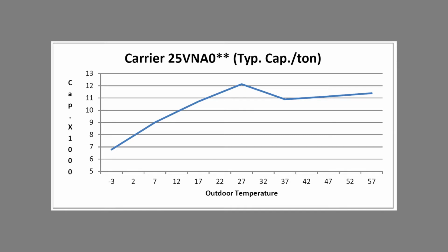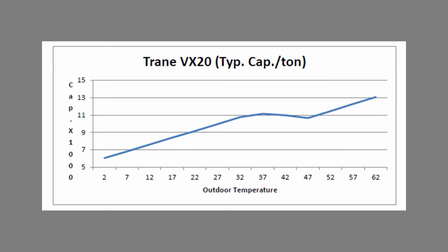But in general, the colder it is, the less capacity the heat pump has. Yes, we now have some extended capacity heat pumps whose curves look very different. Notice that the peak capacity on this system is at 27 degrees. It's actually higher there than it is when it's 52 degrees. Does this make sense? Yes, we don't need full capacity from the compressor at 52 degrees. It's much more likely that we'll need the full capacity at 27 degrees. And we can see that it dives off the colder it gets.